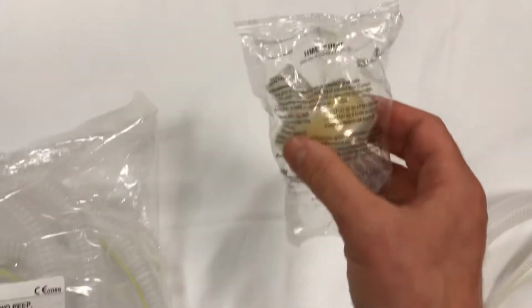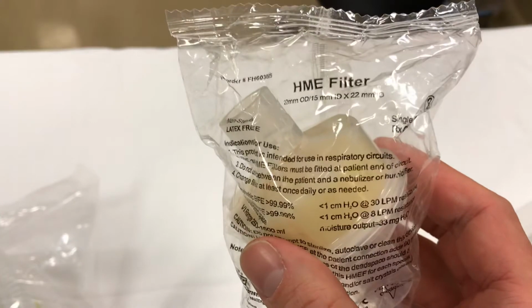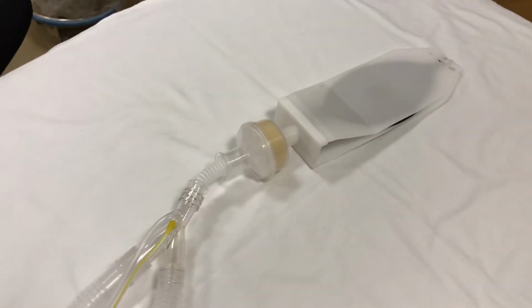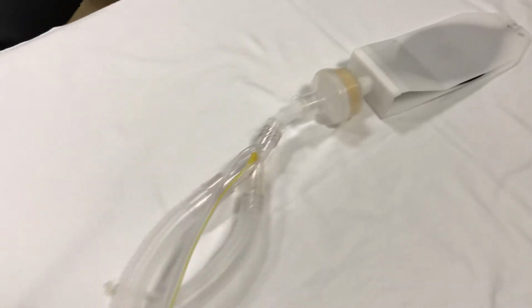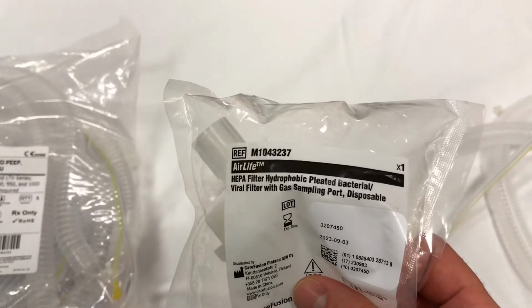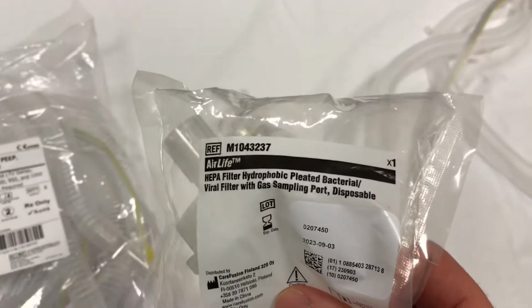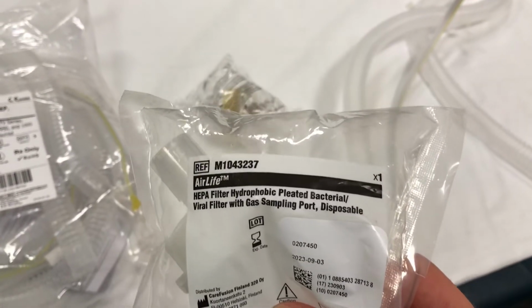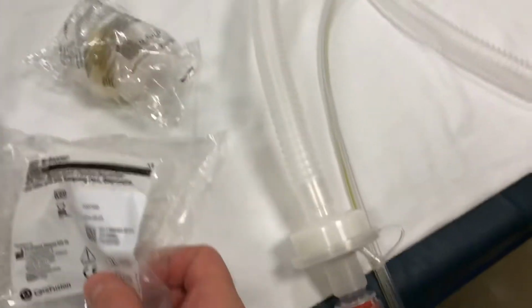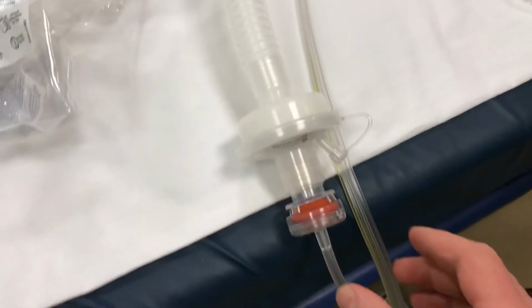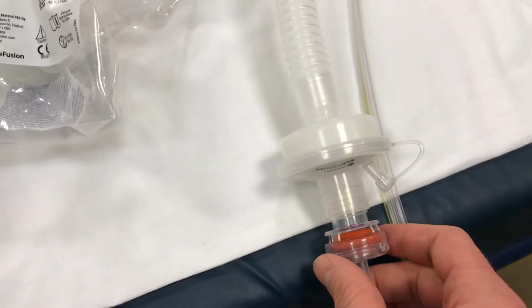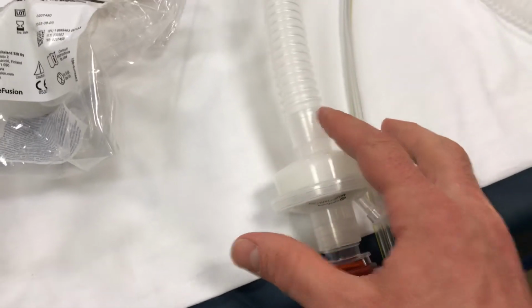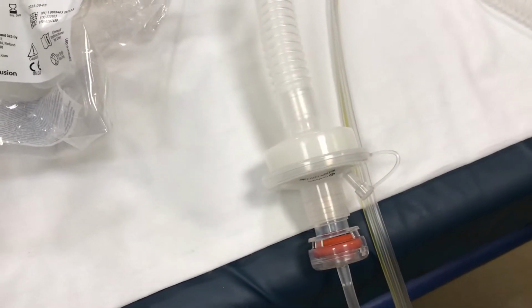talk about a couple different filters. First is our standard humidifying filter. This actually goes to the end facing the patient. Next, we have our hydrophobic HEPA filter, also known as the viral filter. This is actually connected between the exhalation valve and the corrugated tubing in the expiratory circuit.